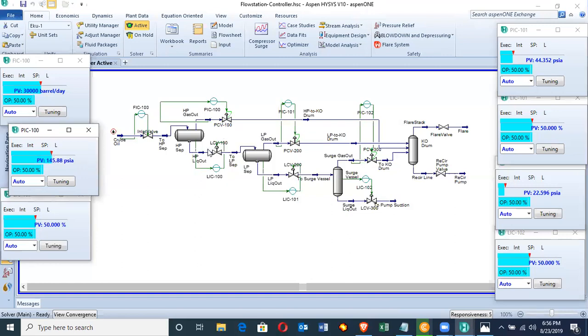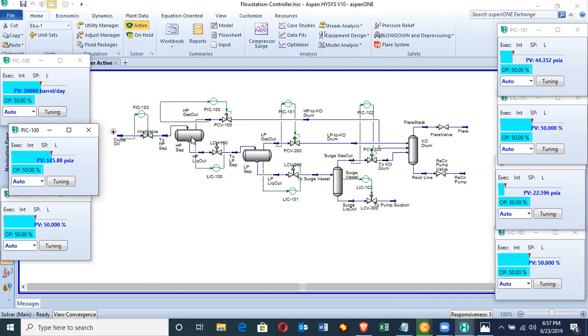Likewise, for the level of the separator, in engineering design separators are assigned 50%. If the level is above 50% or below 50%, the difference sends the appropriate signal to the level control valve actuator to either open more than 50% or reduce more than 50%. And this is how you control the level in the separator.